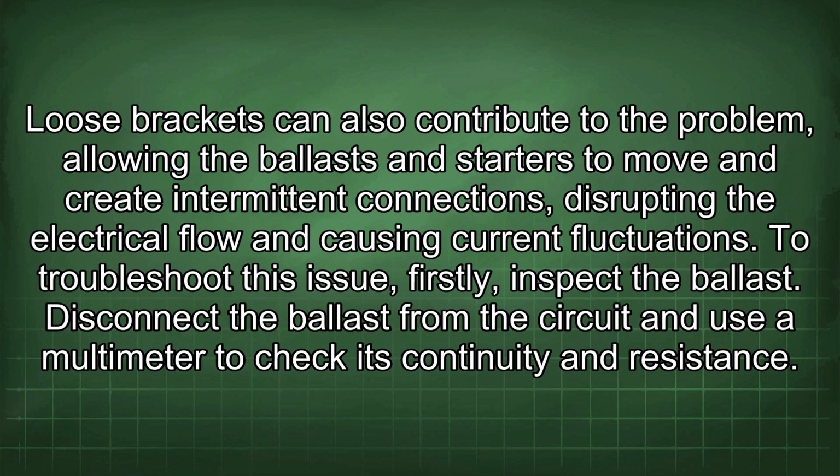Loose brackets can also contribute to the problem, allowing the ballast and starters to move and create intermittent connections, disrupting the electrical flow and causing current fluctuations.